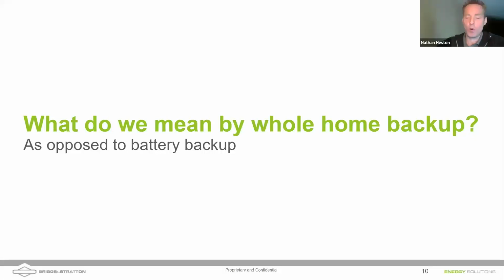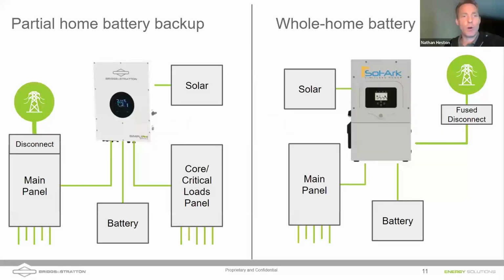What do we mean by whole home backup? So I've got a slide here, and this slide is going to show us what happens in a grid down situation. So if you look, both of these are grid tied systems. Both of them have batteries. Both of them have an inverter. On the left side of the screen is a Briggs & Stratton inverter, and this inverter is a smaller inverter. It's 6 kilowatts maximum output.